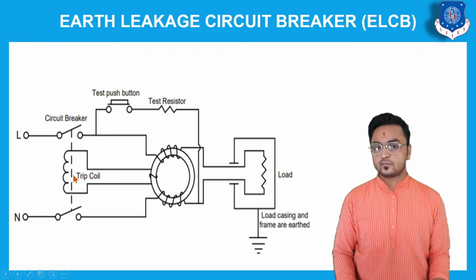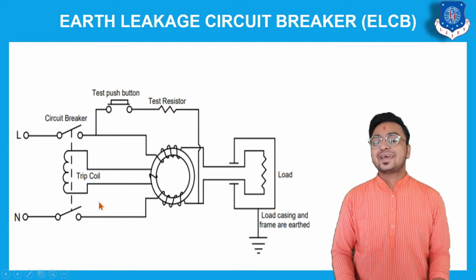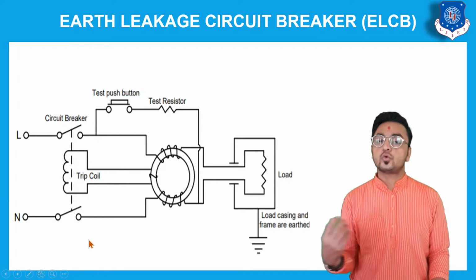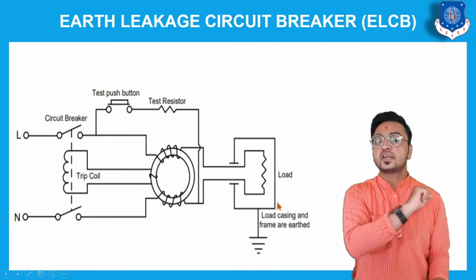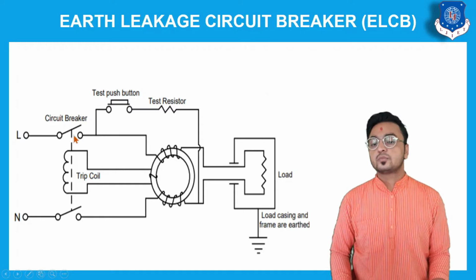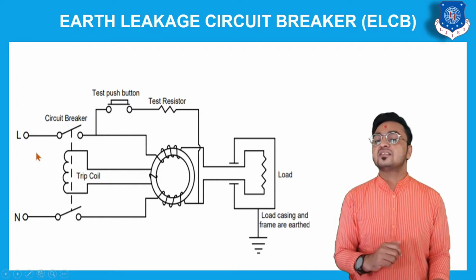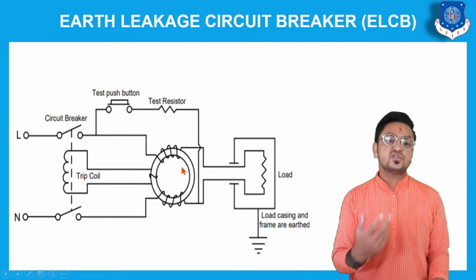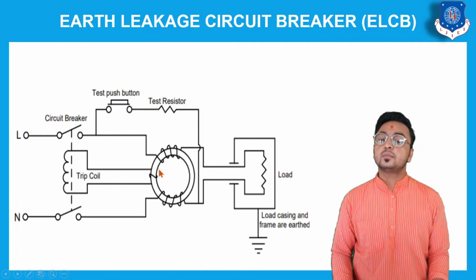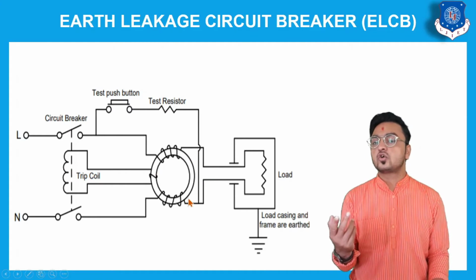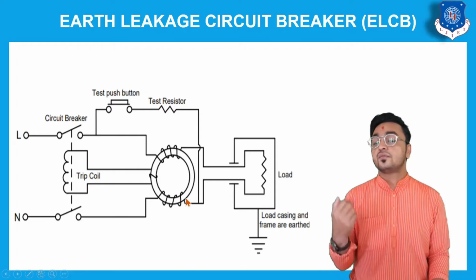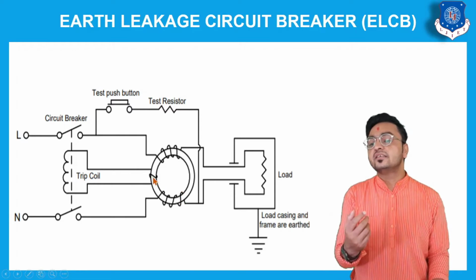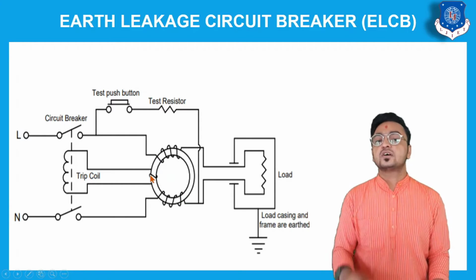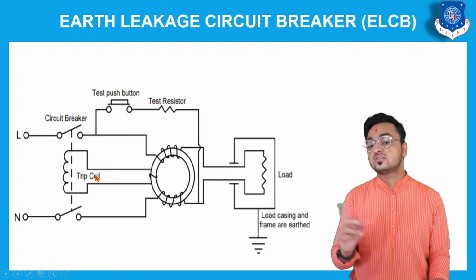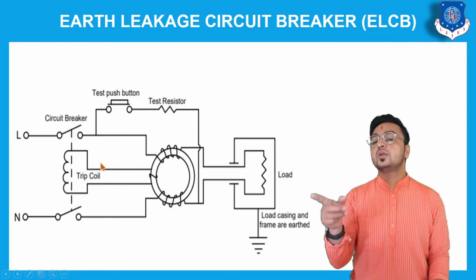We had arranged a mechanical switch on the path from which we provide supply to the circuit or load, and this switch can be operated by the trip coil. When there is a current difference between the two coils, it produces a flux difference and resultant flux, which generates EMF for the trip coil, and the trip coil operates.